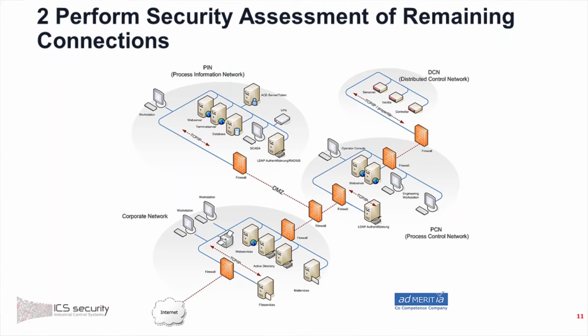I want to emphasize: a SCADA network is only as secure as its weakest connecting point. You can implement a strong cybersecurity strategy, firewalls, data diodes, DMZs—but if you have just one weak connection, for example for remote support for your integrator, then your entire control system is as weak as that simple connection. So you need to upgrade all connections in your control system. It's essential to implement firewalls, intrusion detection systems, and other appropriate security measures at each point of entry.